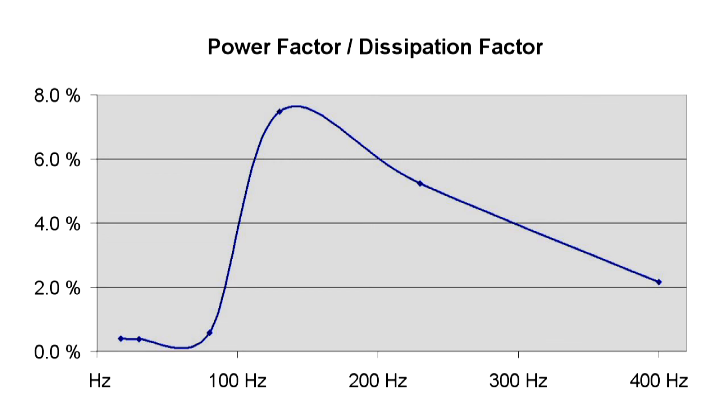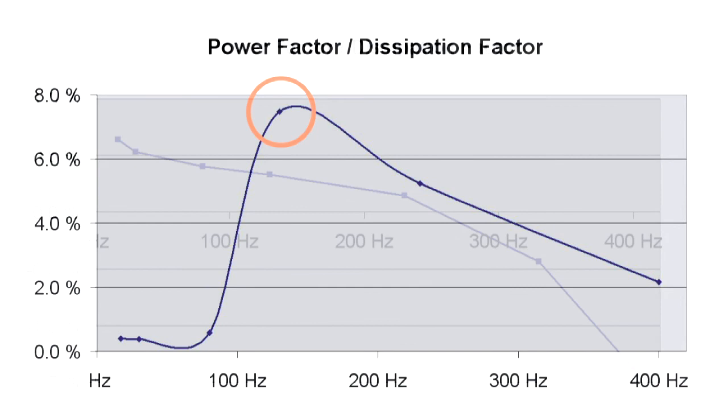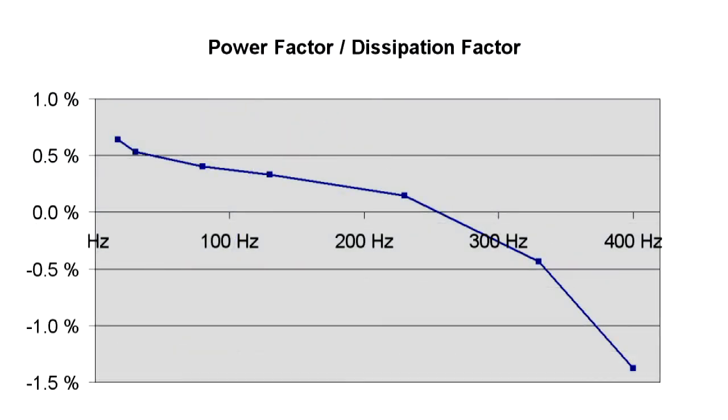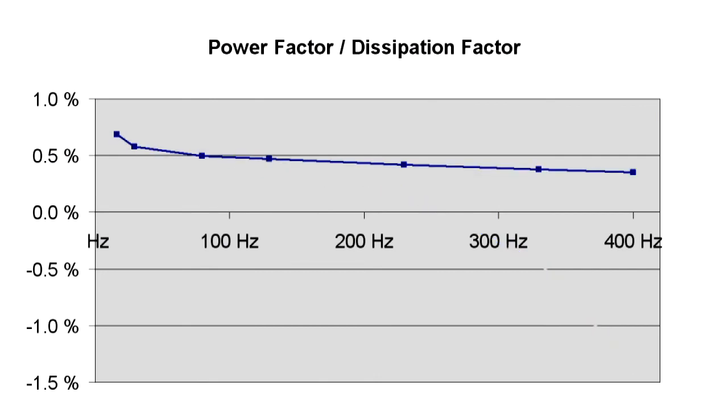If the phases of a winding are not properly connected, or not connected at all, the dissipation factor or the power factor may display a peculiar progression. This curve even displays negative values at around 250 Hz. This is what the curve looks like after the contacts have been cleaned and the bushings were connected to each other.